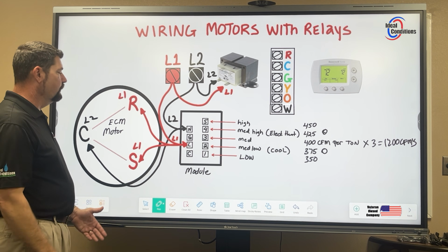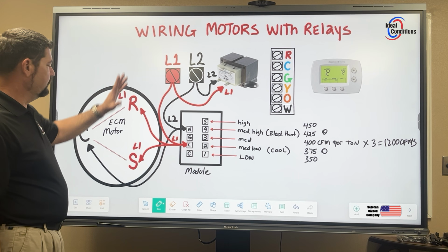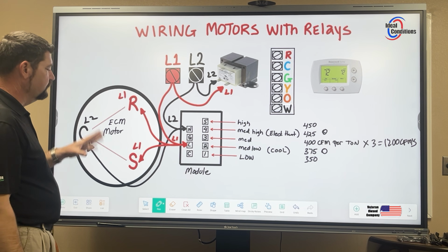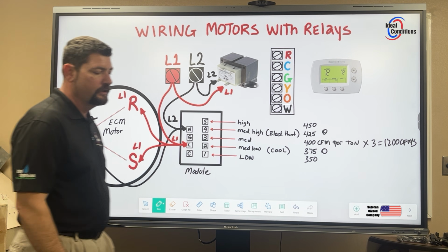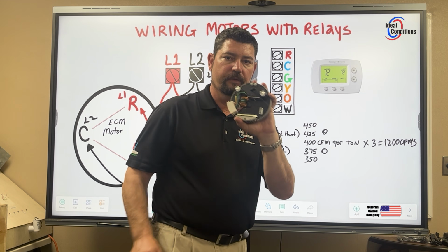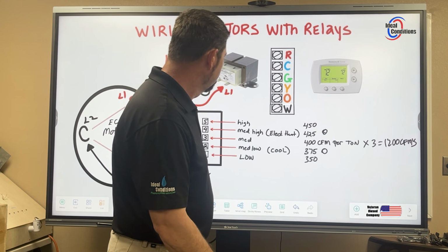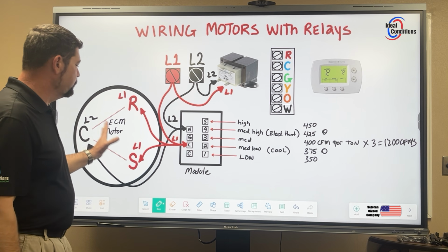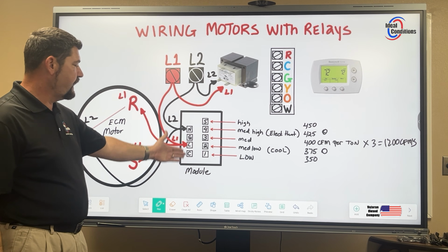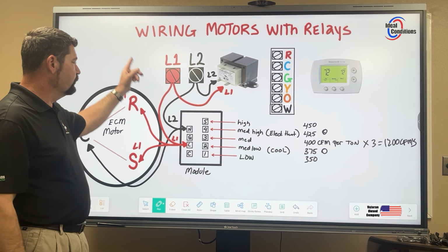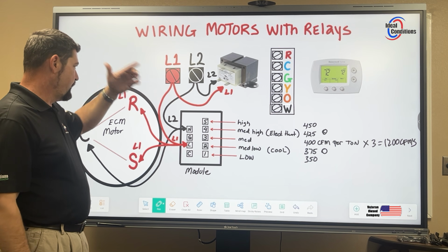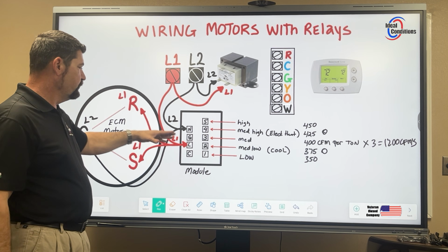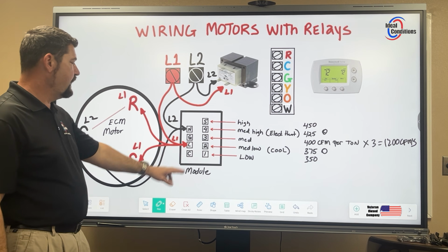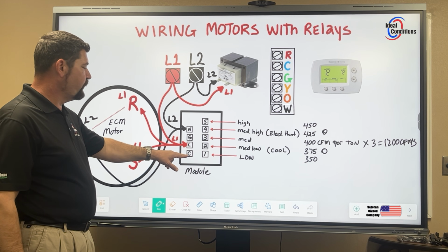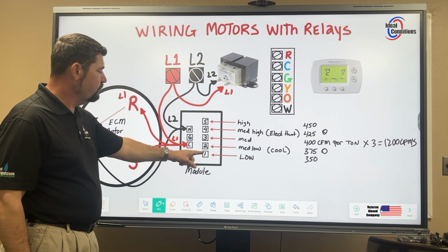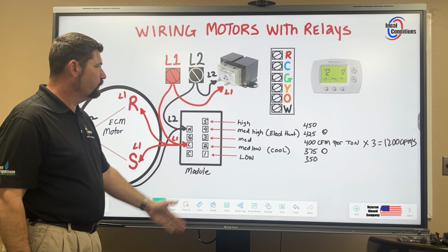So now you still know that these 2 windings are off of 1 leg. This winding is still off of another leg. There's just no capacitor for me to show you because all that's happening through the module now. There's nothing else high voltage that we have to wire. We wired that portion. The G will go to ground. I don't have ground up here in my diagram, but G will go to ground. We have common. This is not a high voltage common. This is a low voltage common. And then 1 through 5 are all 24 volt inputs.